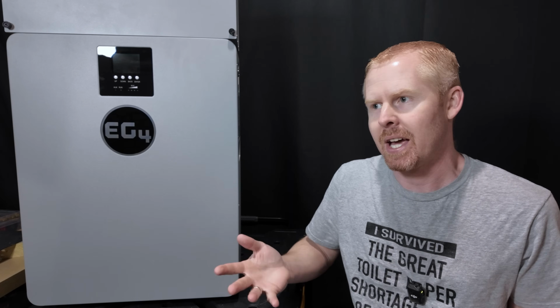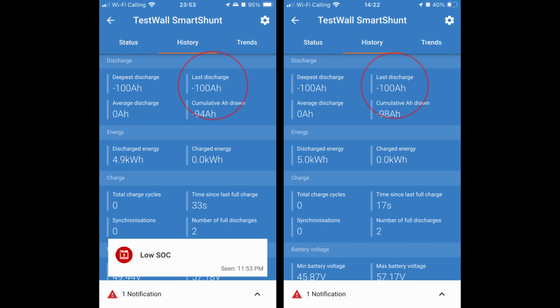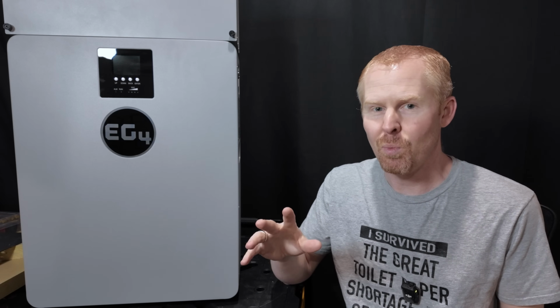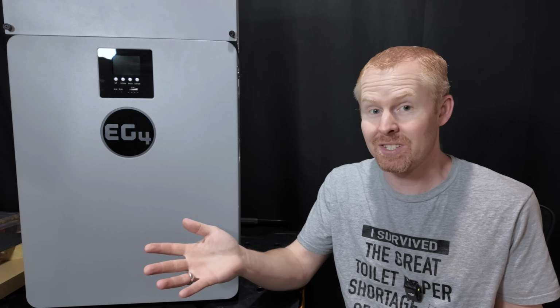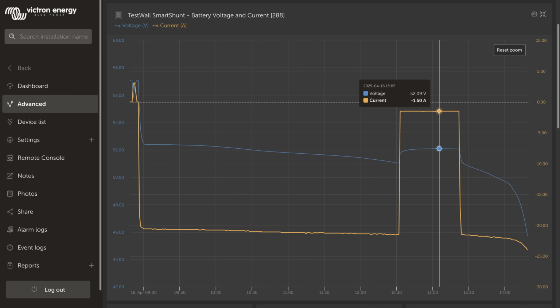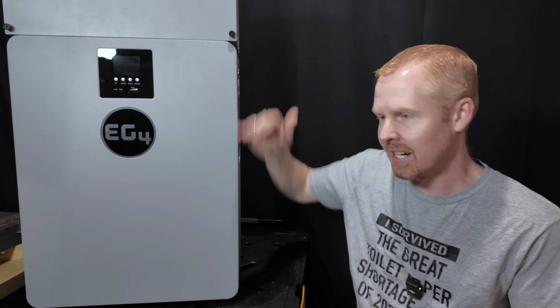So I did end up running the capacity test on this battery 2 more times, and both of those times I did reach the rated 100 amp hour capacity. Now, full disclosure, during both of those tests I had some issues where my inverter kept resetting its low disconnect voltage level. It would end up hitting like 50 volts, and then my discharge test would stop, sitting that way for about 45 minutes to an hour each time. So the battery had plenty of time to spring back up to its resting voltage. Once I found that out, I reset the test again, and it hit that 100 amp hour discharge.